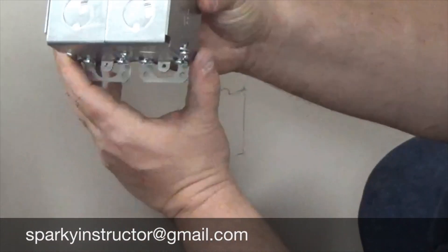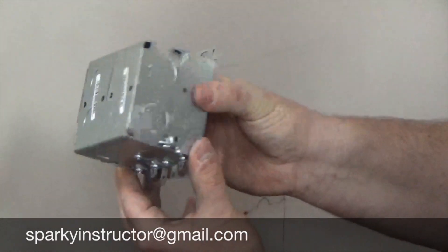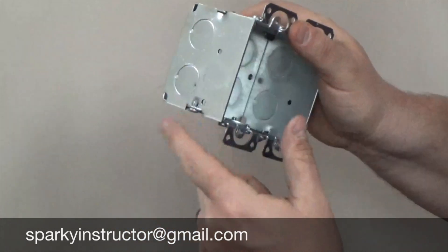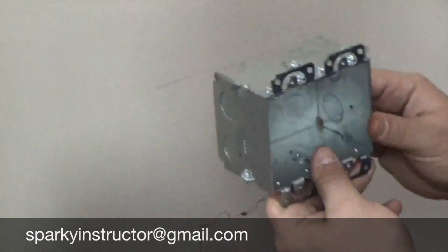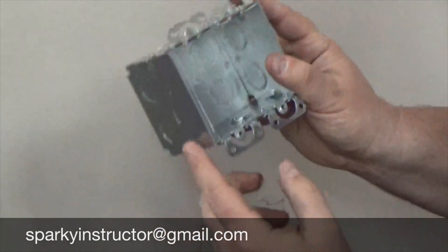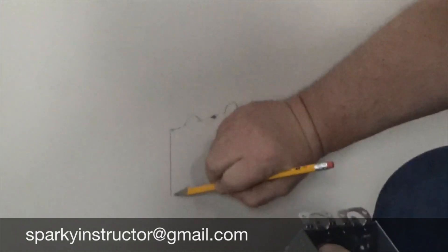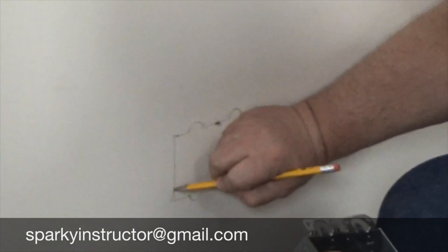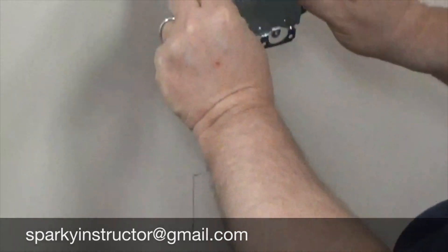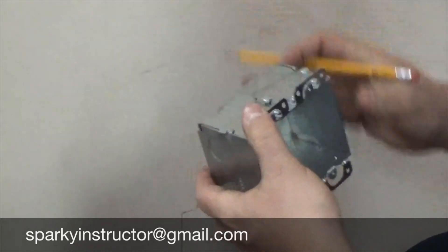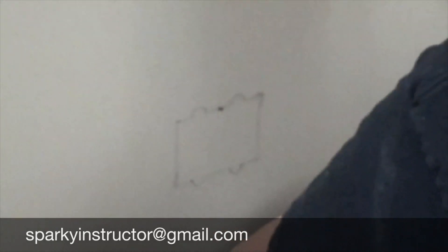Now, when you look at an old workbox or the side, you can see, remember where I showed you where those screws are? They actually stick out a little bit. So what we're going to do is when we slide it in the box, we're going to actually notch for these screws and they are catty corner. So what you're going to want to do is you're going to want to notch out just a little area on these sides here so that the box will sit in nice and comfortably. Plus when you stick your Madison strap in, you're going to want to know which way you want your wing to flip up. So let's cut it out.